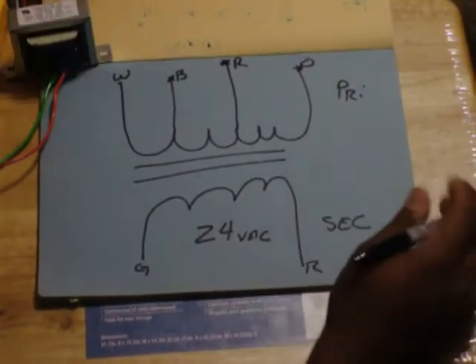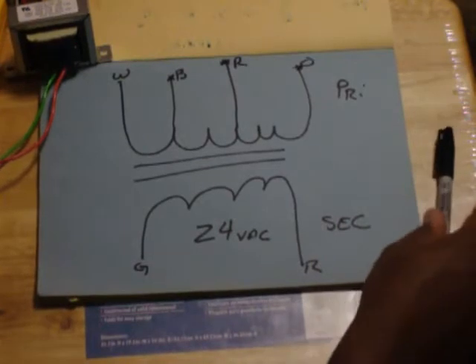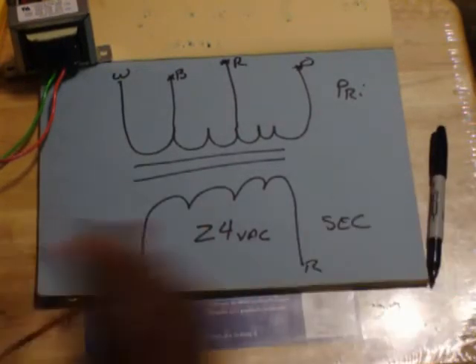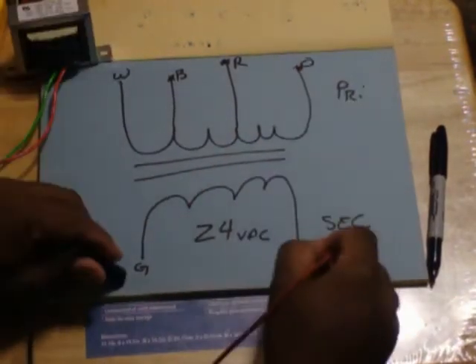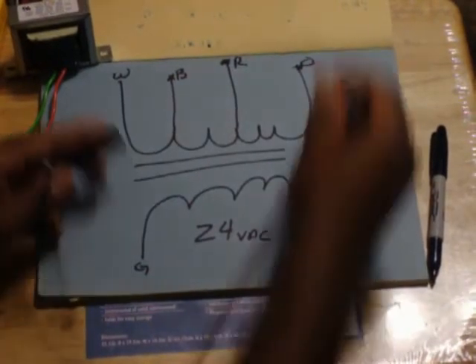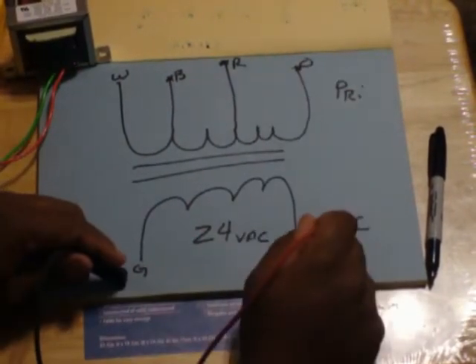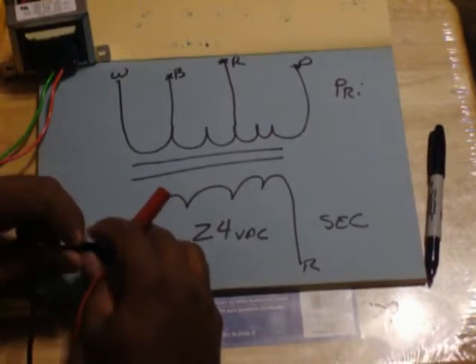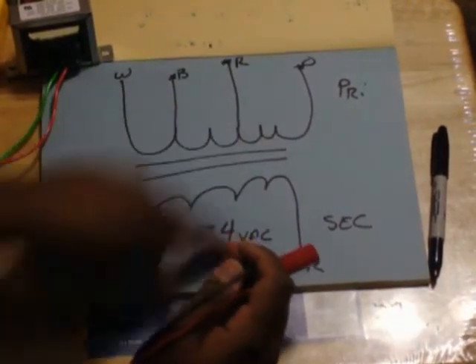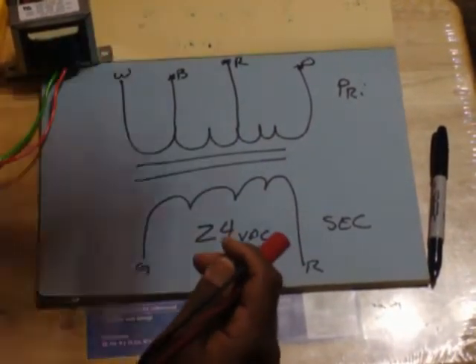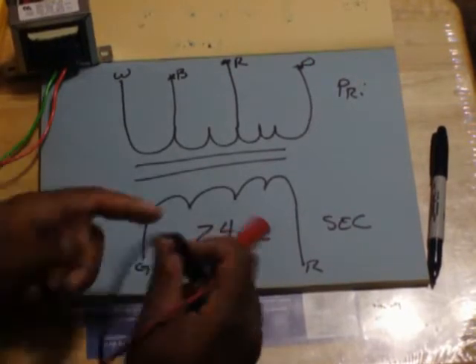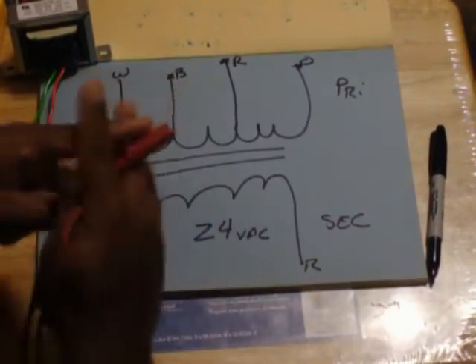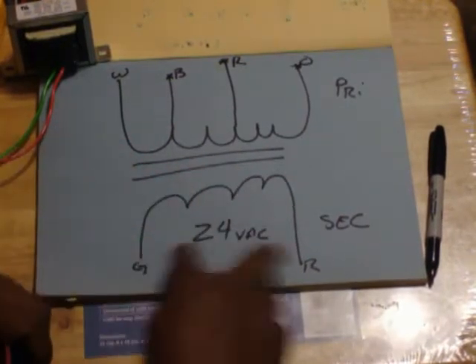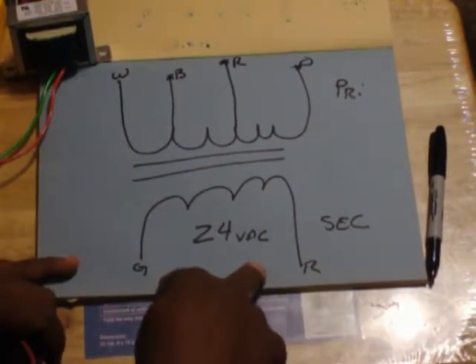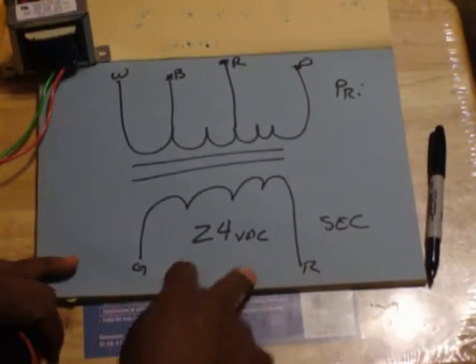Checking this is very easy. If you want to check it with power applied to it, you simply check power going in and power coming out of it. If you have power going in, you don't have power coming out of it, it's bad. It's important to know which side is burnt out. If it's your secondary side burnt out, you have a load, a contactor, a relay. One of your wires could be rubbing together. I've seen them go to the condensing unit, rub together, and short out. Something down here that this feeds is shorted out.